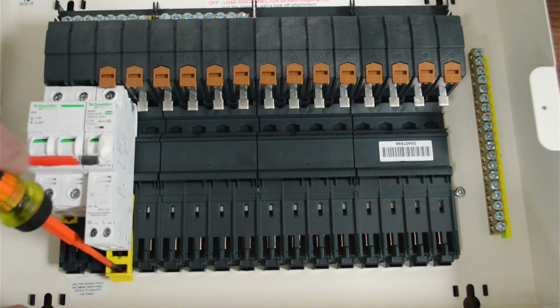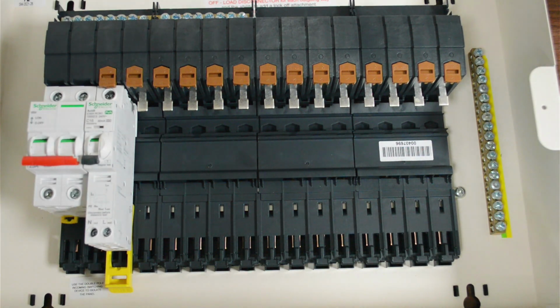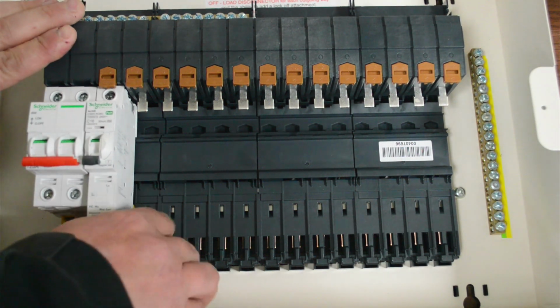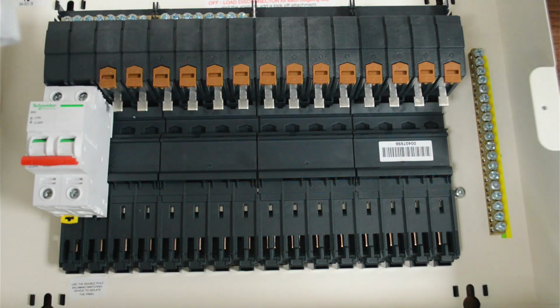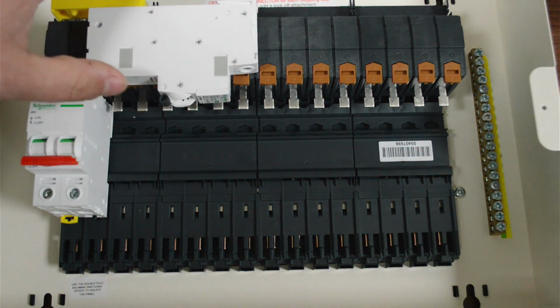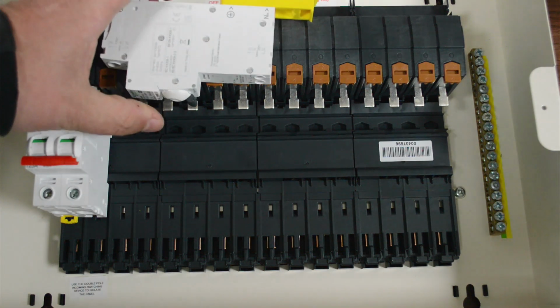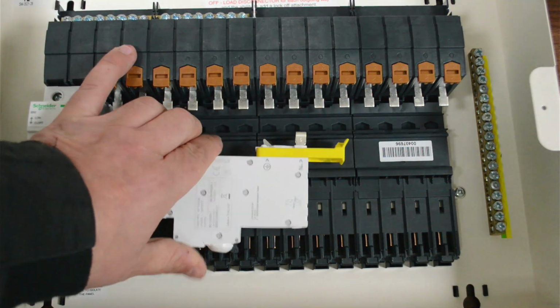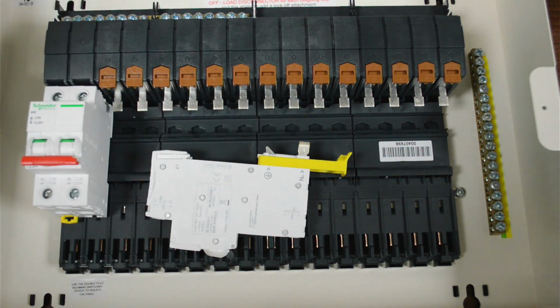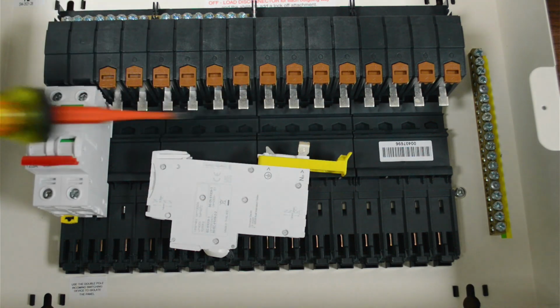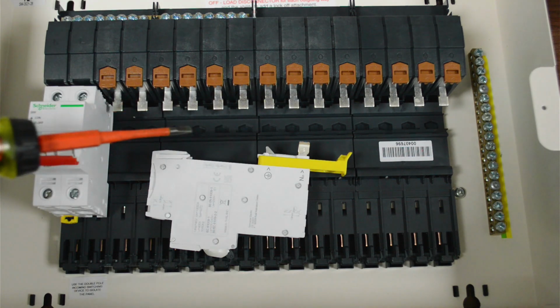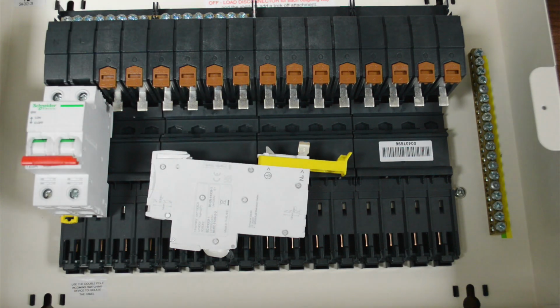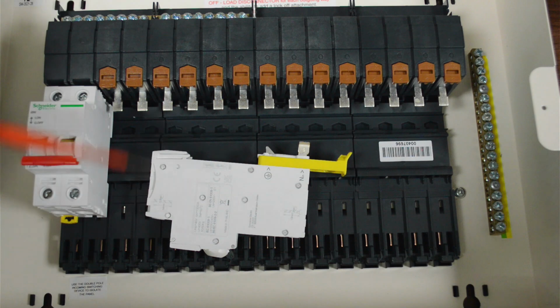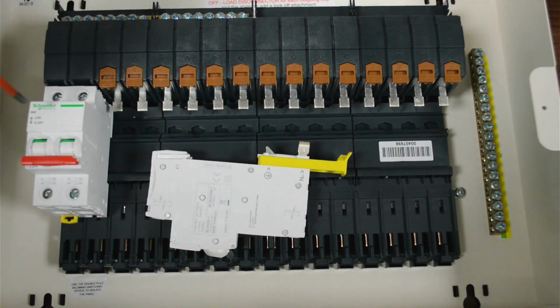And then equally, if you pop the yellow tab back out on the bottom, it simply pulls out, up and away, and then you can drop in whatever you need to. So I like that. I think that's a pretty safe way of connecting in equipment, because you have got the isolation, if you like, of the busbar itself for somebody who's maybe working inside the enclosure, and you're not in a position to isolate the incoming feed onto the main switch itself.